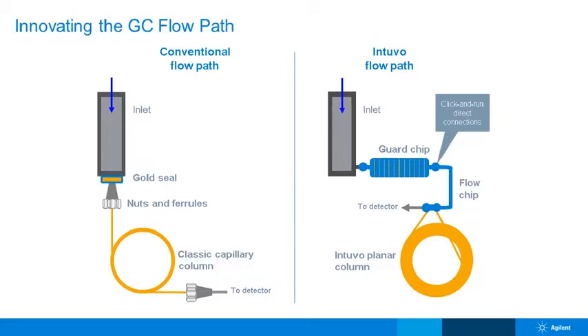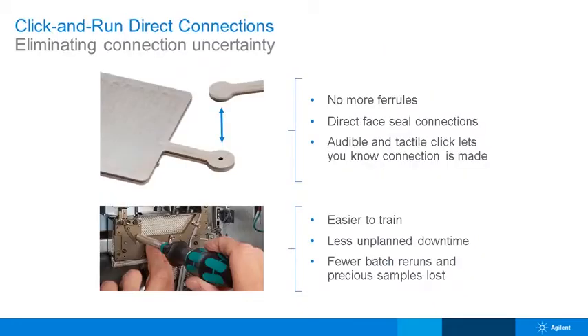So a completely different flow path. Traditional flow path, where you see normally of all GCs out there in the marketplace, you will see bits of capillary column at the base of the GC. You see ferrules everywhere, you see nuts everywhere. GCs don't tend to be a neat place to be. On the Intuvo flow path, we have got rid of those nuts and ferrules, and we don't need to cut the columns. Obviously it's a completely different flow path, and we're making connections by basically click and run connections where you're deforming the metal to make it. So it's actually inherently more gas tight than you'd ever get with a ferrule.